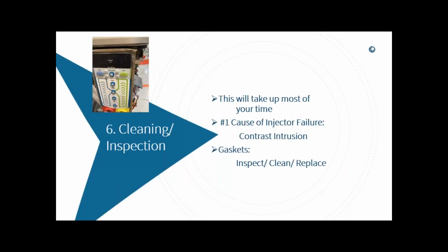Cleaning and inspection. This will take up most of your time. Contrast intrusion is the number one cause of injector failures. And how do we get contrast intrusion? Is it the customer always? The user? Well, typically yes. But if the PM is not done properly and you have bad gaskets, it's even more of a problem. If you have good gaskets, it's less of a problem, because the gaskets are doing their job.